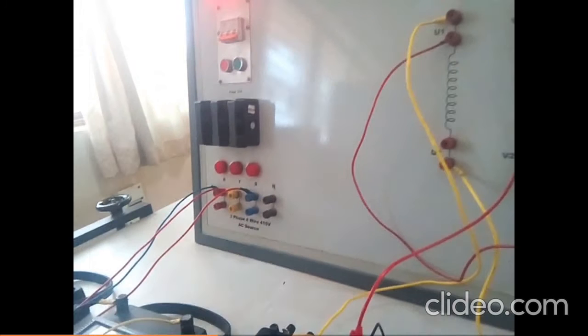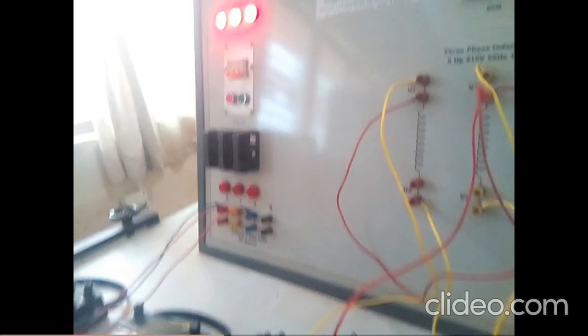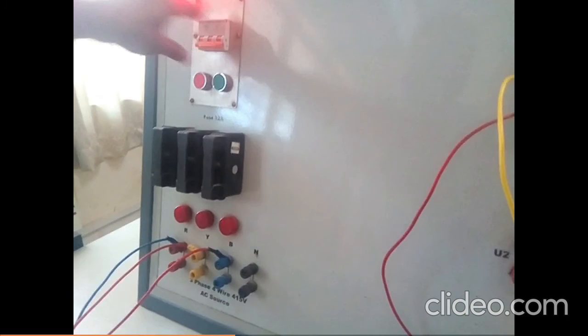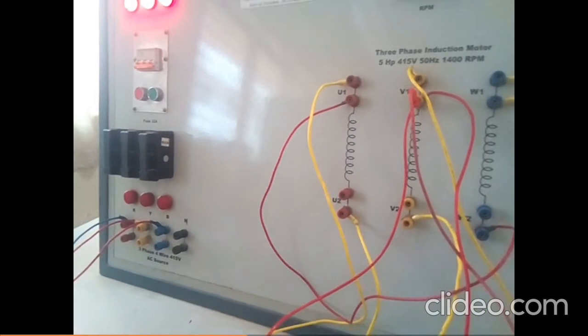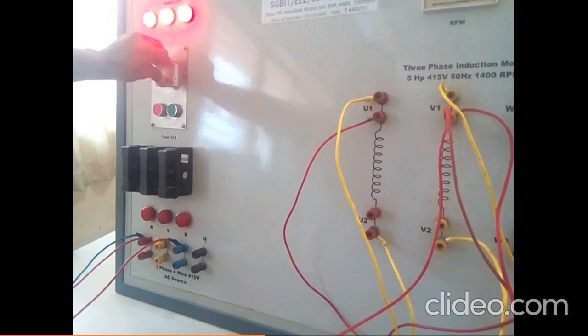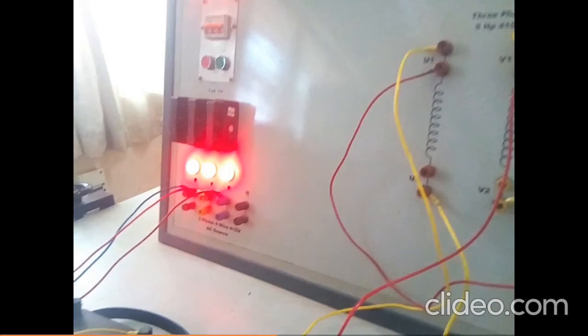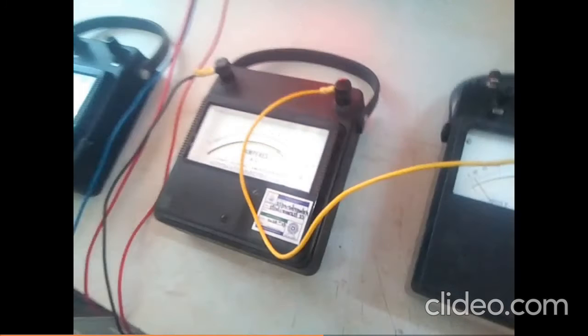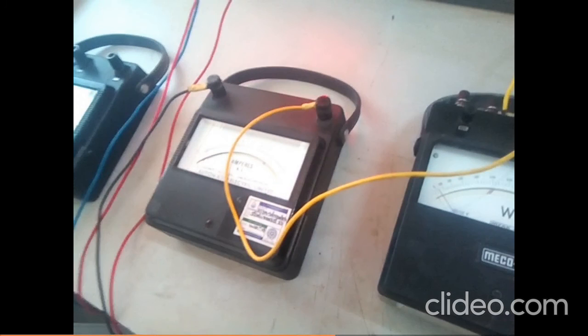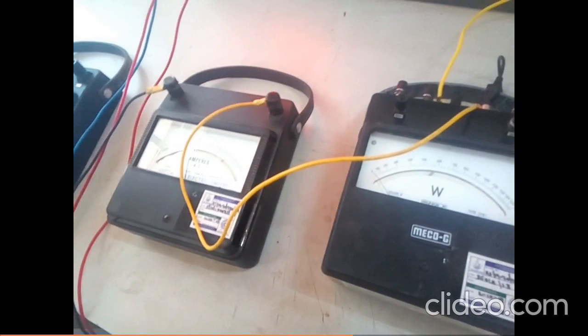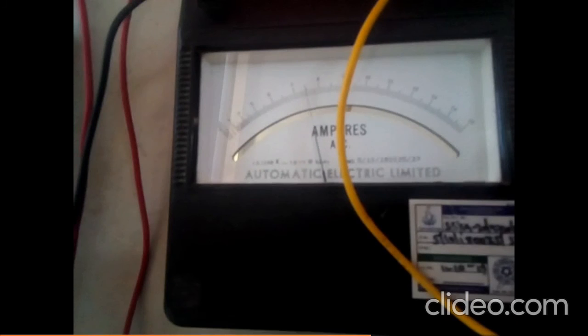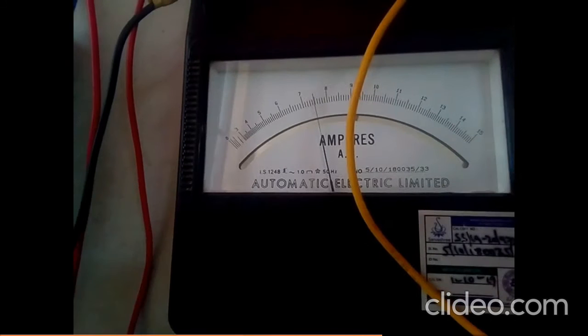After that we conduct the test by switching on the main supply, by switching on the main MCB. You can observe the supply is connected to the three-phase auto transformer. Using the three-phase auto transformer, we apply a reduced voltage to the induction motor to get the rated current in the ammeter. The rated current of the induction motor is 7.5 amperes, and we are observing 7.5 amperes here.